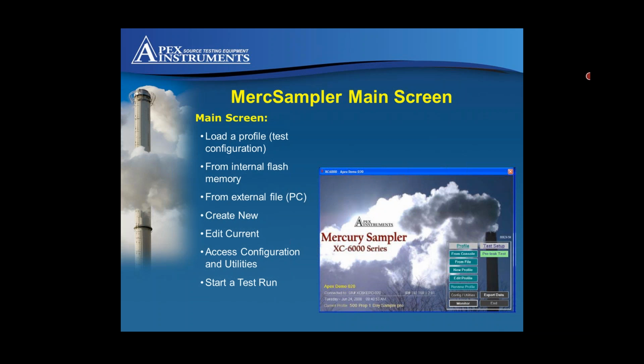Once the profile is built, on the right-hand side where it says test setup, pre-leak test, it's going to step you through one step at a time, keeping you in sequence to make sure that you follow all the steps to actually get your run going.